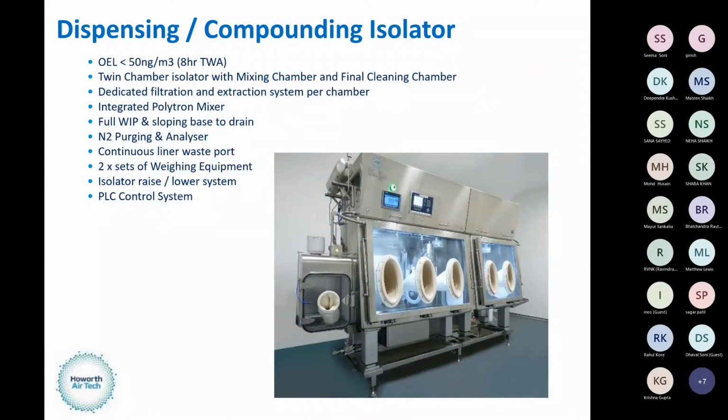So when we get into the high containment applications, we'll always do a containment performance test. So this is really a couple of examples of the results. And this is really important for me because this shows that we can give you the performance you need. And without that data, it's very difficult to say if the system you're using is going to be the correct system. So you really need to get the proof that these systems will work.